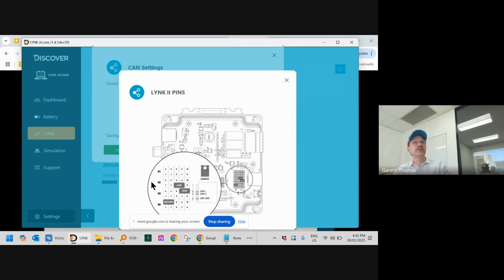When you're doing Victron, instead of changing these pins, you can just use the Type A cable, which will transform them from being on pins 4 and 5 to being on pins 7 and 8, which is what Victron requires. So you don't need to change the pins for this. For NOARC and Victron, you don't need to go through this process unless you want to use a normal cable—you can just use a normal RJ45 cable anyway. It's only for Selectronic, which have their pins on 1 and 2, that you need to move these jumpers down.